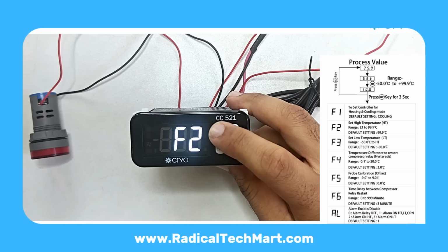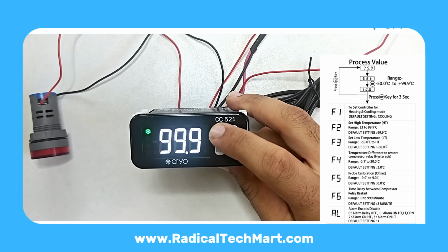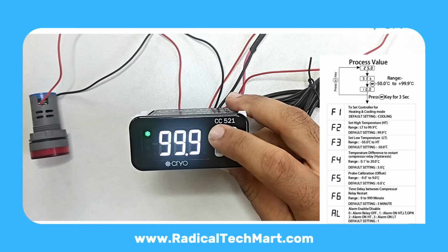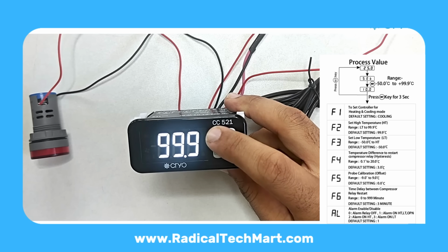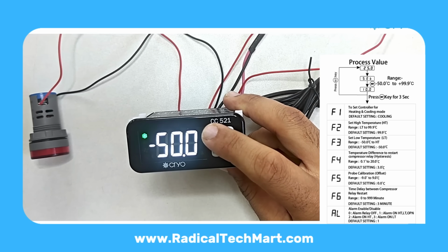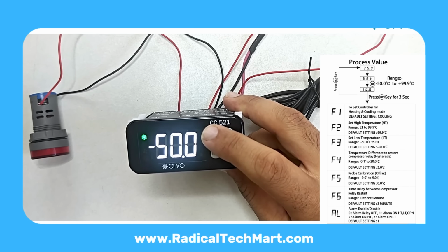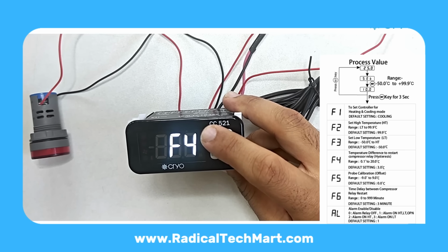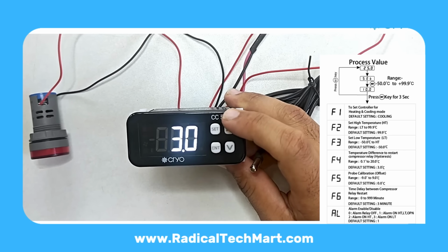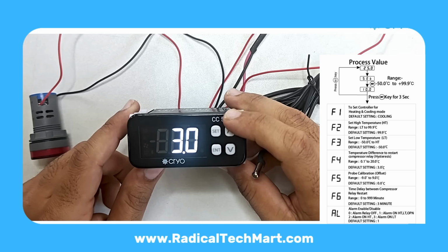F2 High Temperature Limit. The maximum temperature you are allowed to set as a set point. You cannot set any value above this limit. F3 Low Temperature Limit. The lowest allowable set point. F4 Tolerance, a hysteresis. This defines the temperature band for relay on-off.